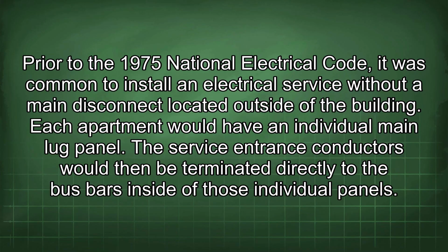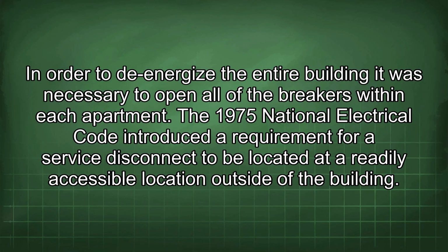Prior to the 1975 National Electrical Code, it was common to install an electrical service without a main disconnect located outside of the building. Each apartment would have an individual main lug panel. The service entrance conductors would then be terminated directly to the bus bars inside of those individual panels. In order to de-energize the entire building, it was necessary to open all of the breakers within each apartment.